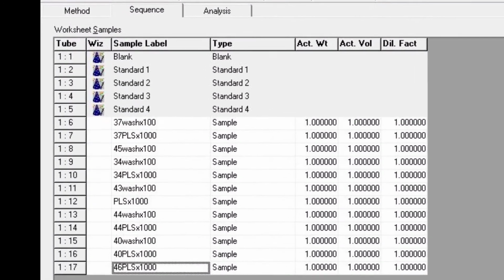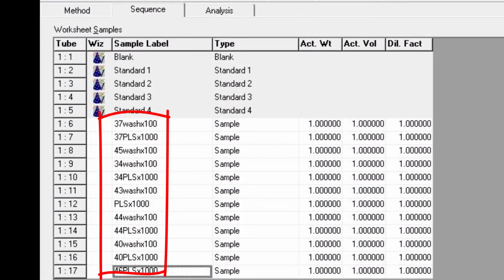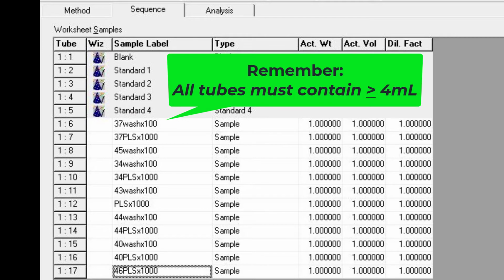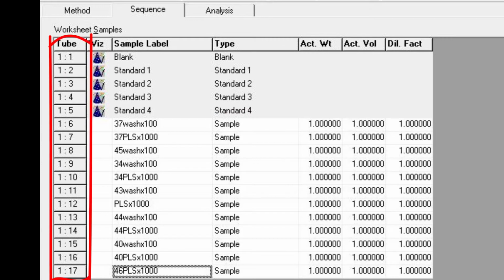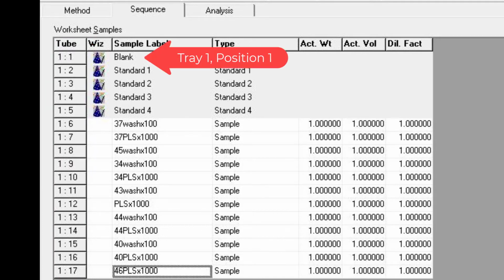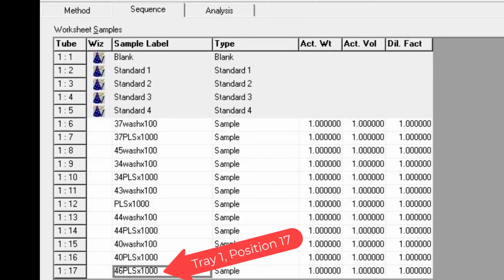In the Sequence tab, enter your sample names in the order you will insert them into the sample tray. This is also the order in which the samples will be run. Remember that you need a minimum of 4 milliliters in your centrifuge tubes to run. The leftmost column shows you where the samples in standard tubes need to be placed on the tray. As you can see in this example on the left, we are using tray 1, starting with the blank in position 1, and ending with the sample in position 17.